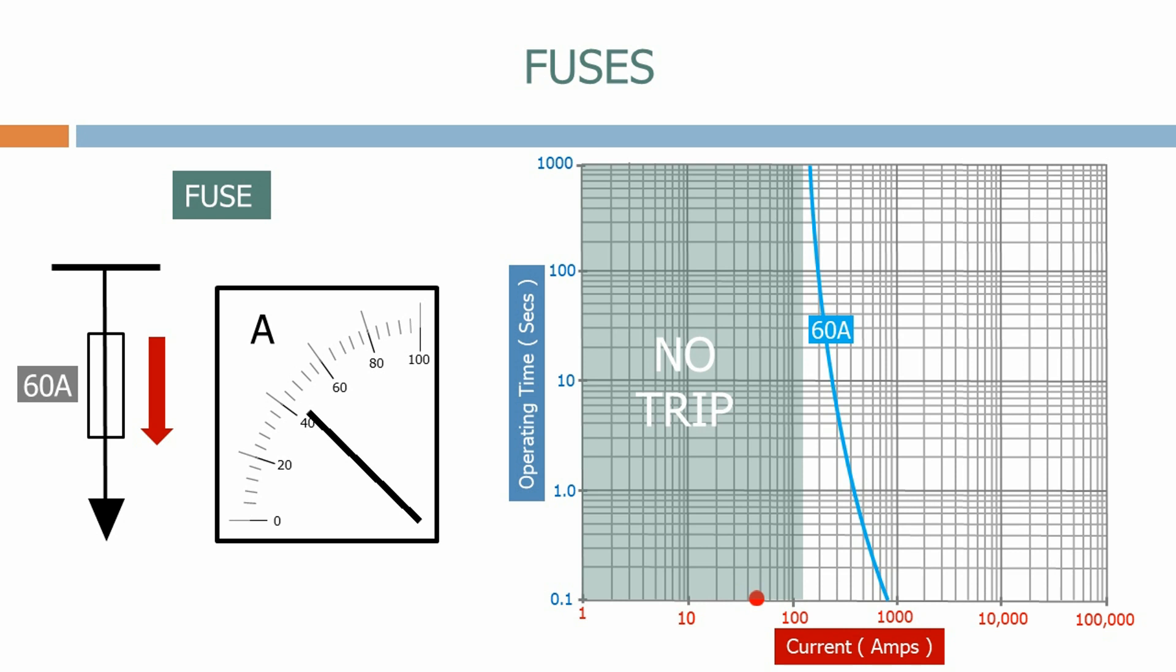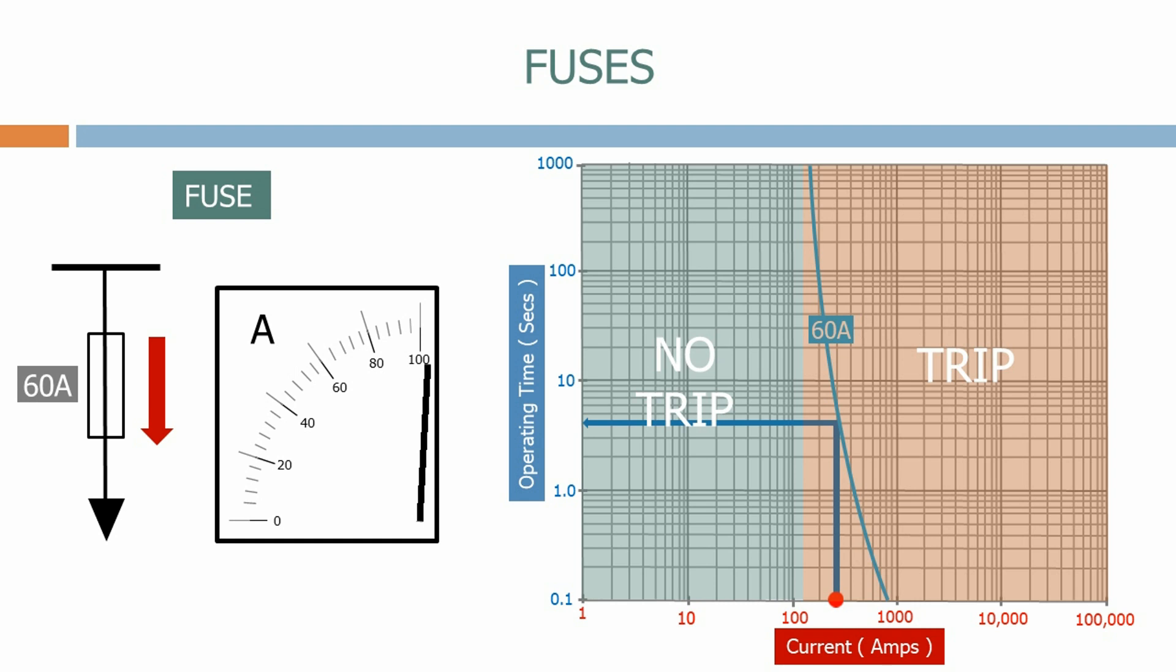Let's now increase the magnitude of the load and see what happens. As the load current steadily increases we leave the no trip zone and enter the next area of the characteristic, which is the trip zone. In this zone the fuse will react. The operating time of the fuse will depend on the level of the current. At 300 amps, the operating time is just under 4 seconds.